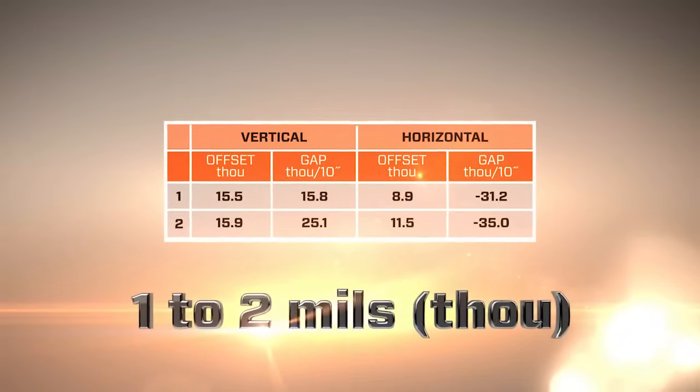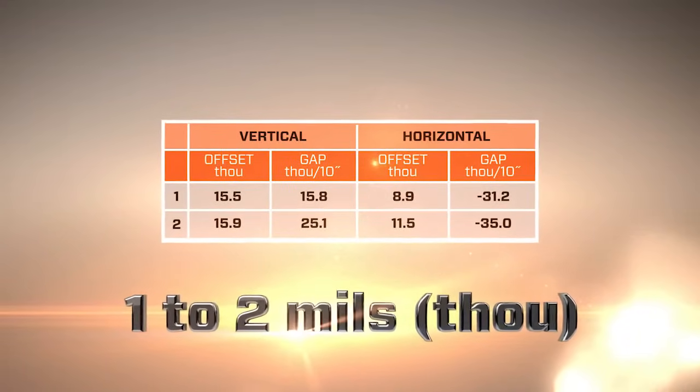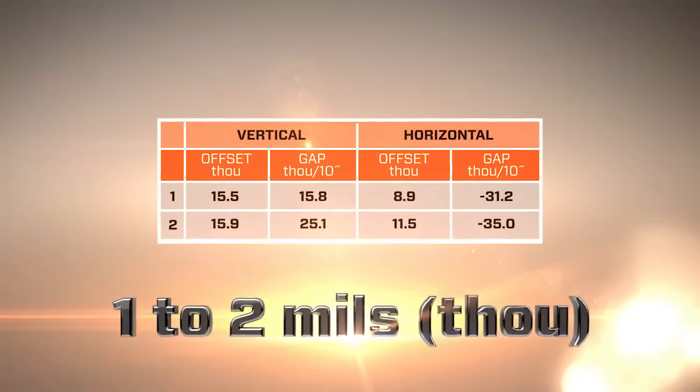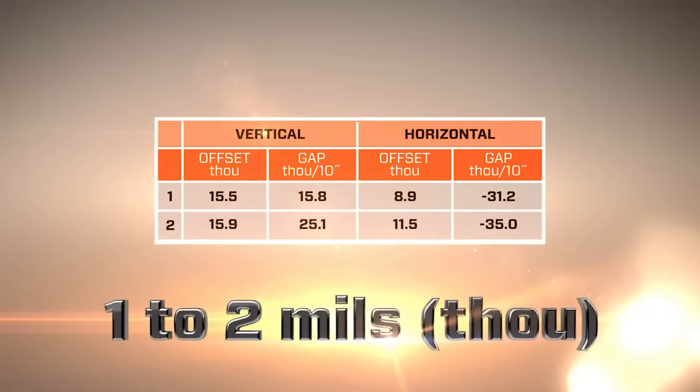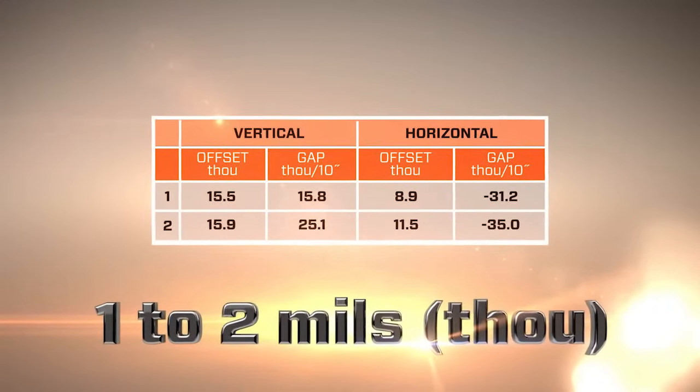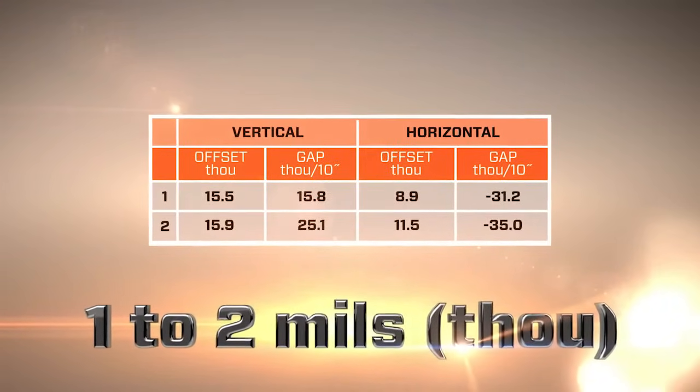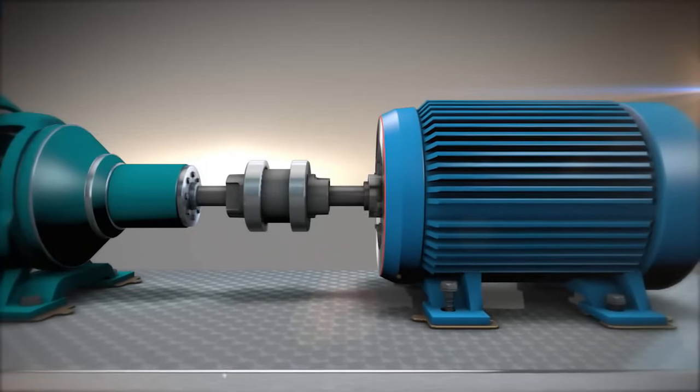Once rough alignment has been performed, the results should be no more than one or two thousandths apart, which is not the case in this example. It makes no sense to proceed with the alignment until and unless repeatable readings have been achieved.